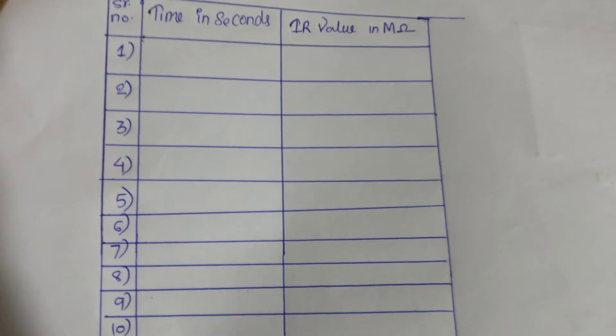The observation table has columns for time in seconds and the IR value. It is a hand-driven generator. We will record the value at 15 seconds, 30 seconds, 60 seconds, and 120 seconds, that is two minutes. From the values we obtain, we can plot the graph for the dielectric absorption test and also determine the polarization index.